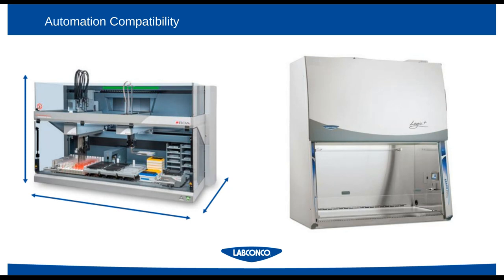So on the screen is a Tecan Evo platform, and roughly these units are about 30 inches in depth. And if you look at the inside of a typical biosafety cabinet, across all different models out there, you'll see a number of dimensions listed, but the working depth is typically representative of the work tray or the actual space available in the enclosure. And even though some instruments may fit into a biosafety cabinet, knowing the compatibility and the dimensional fitment of that unit inside the hood does not necessarily ensure that airflow will remain safe.